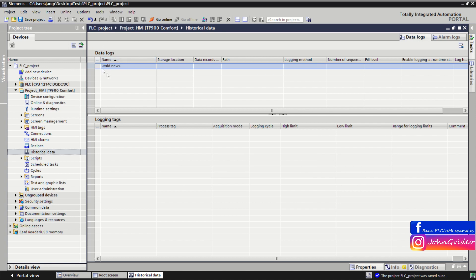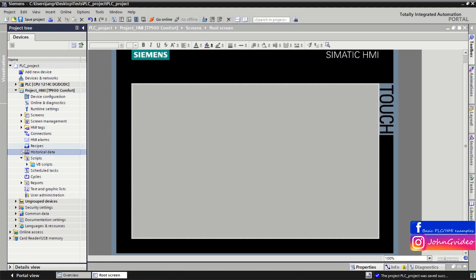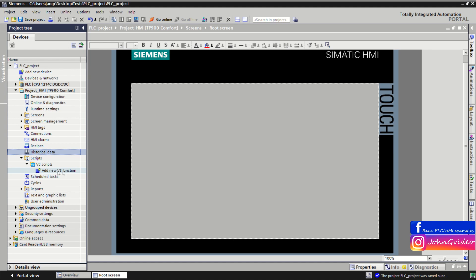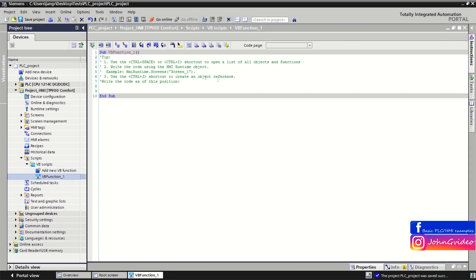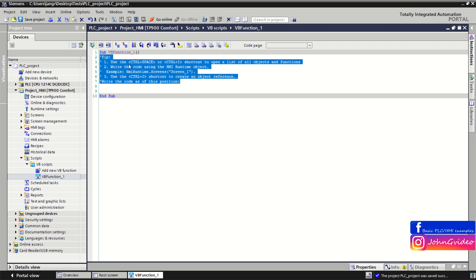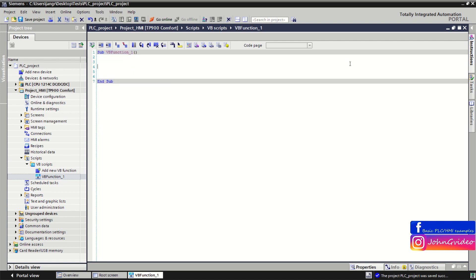In data logs you create a data log, define the storage location, and define which tags you want to log in the Logging Tags window. If you have a Comfort Panel, you can define Visual Basic scripts by clicking 'Add new Visual Basic function' in the Scripts option. You create a new script function and define your code which you want to use in your HMI device.